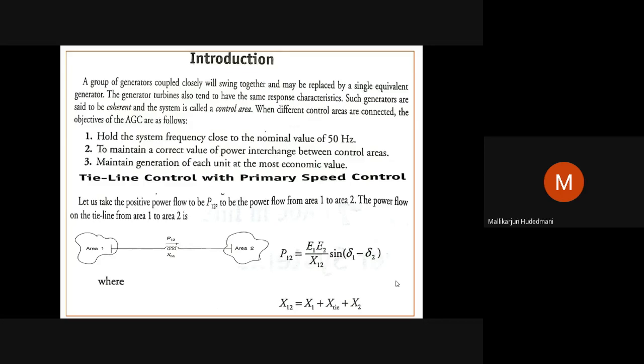For this, you just recall control area control error, a concept we have defined. What was that area control error? Area control error is an error value of a control area, which says whether the generation in that area is adequate and able to meet the requirement of the commitment that that area has made.